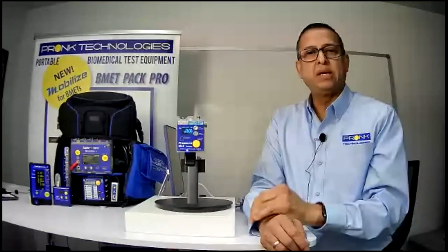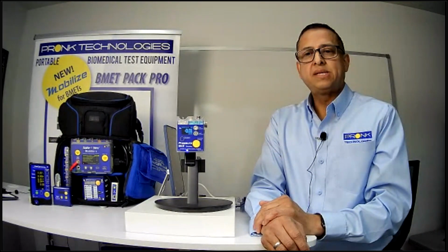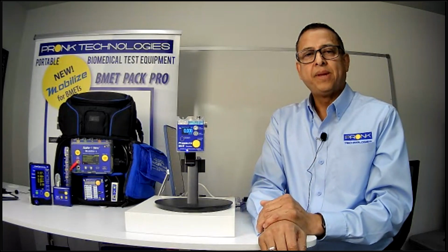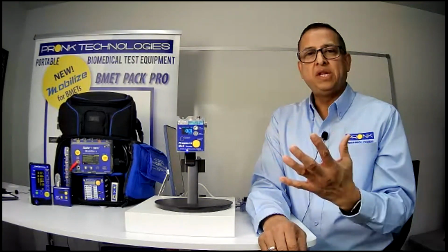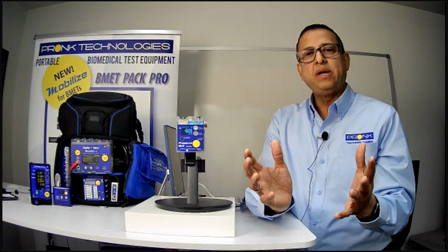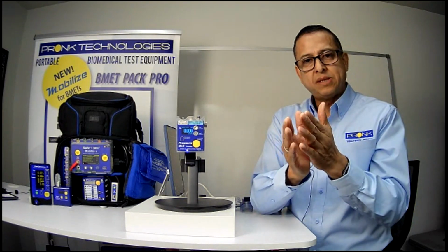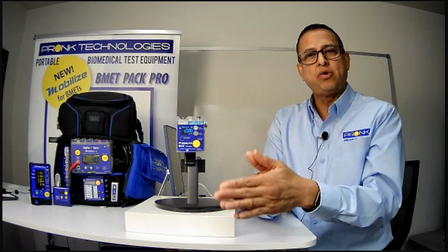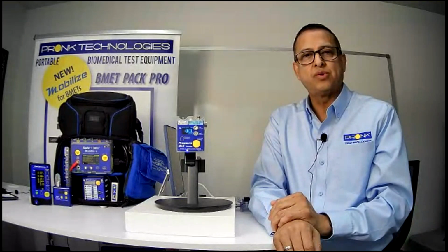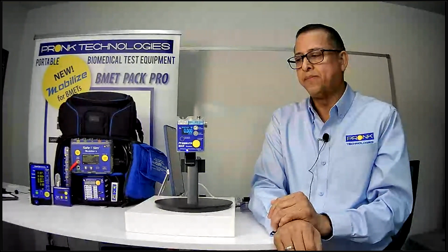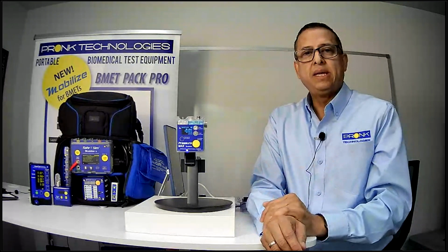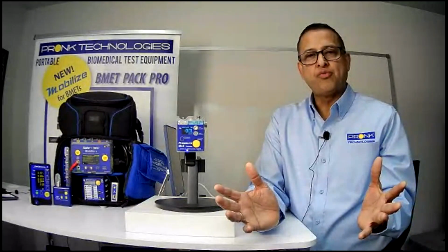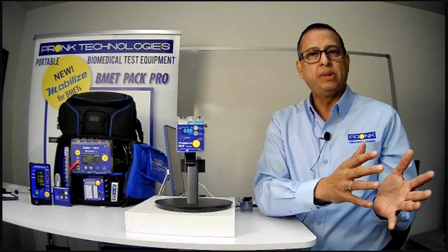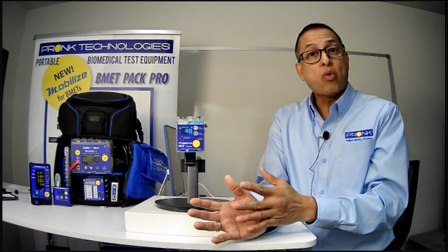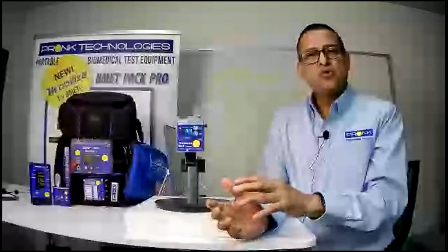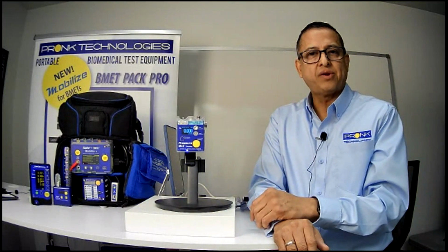And really what initiated the need to design a product like this is the gap in the marketplace with pressure meters. Today, you have a lot of needs for pressure meters that have the range you need for various medical devices, but also the precision and accuracy you need to make sure you're doing that service according to the manufacturer's specifications when you're doing that calibration adjustment. So oftentimes in the HTM community, you have to buy multiple pressure meters. A pressure meter that has X range possibly, maybe a different meter that's got a narrower range but with better accuracy, so that you can utilize it according to the manufacturer's requirements.